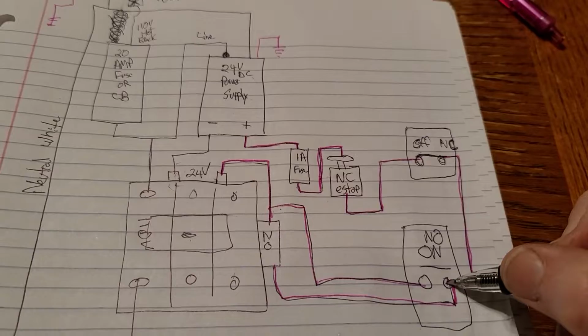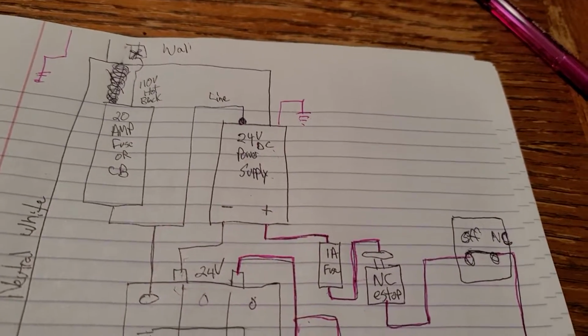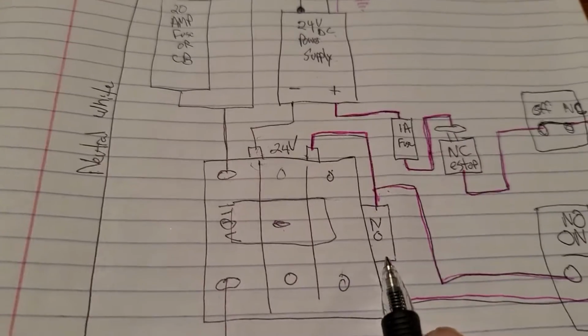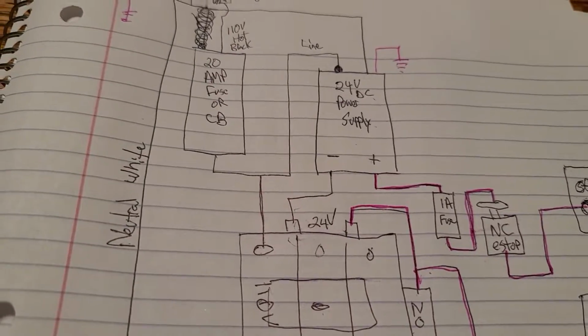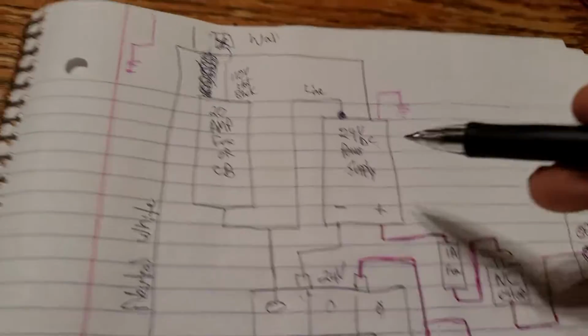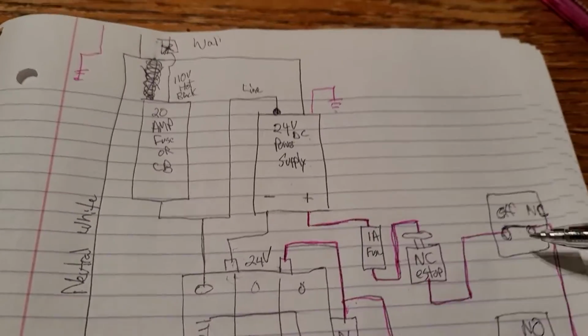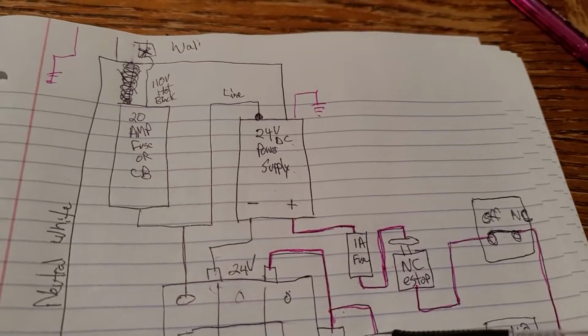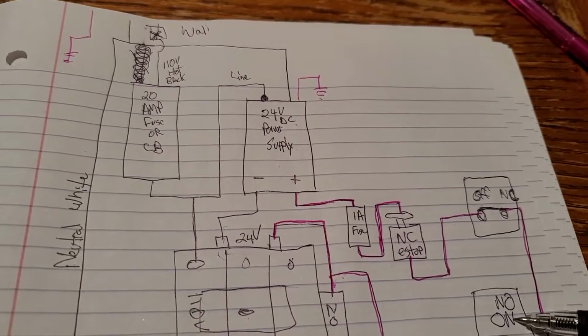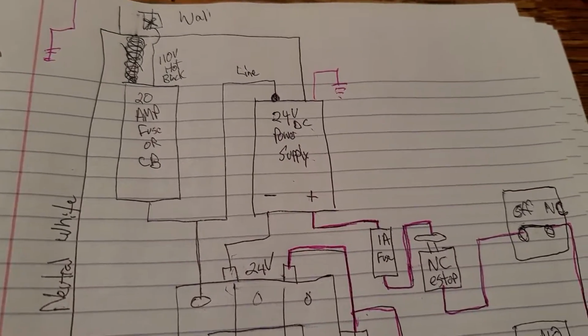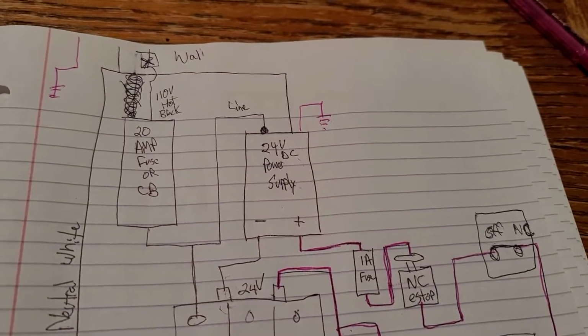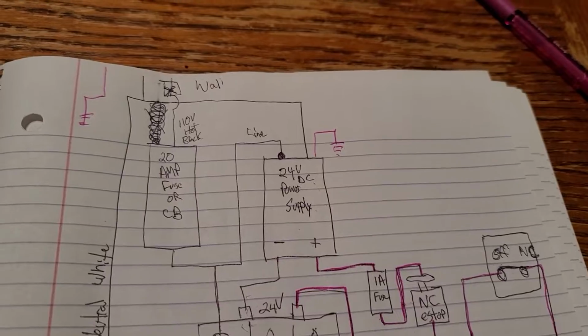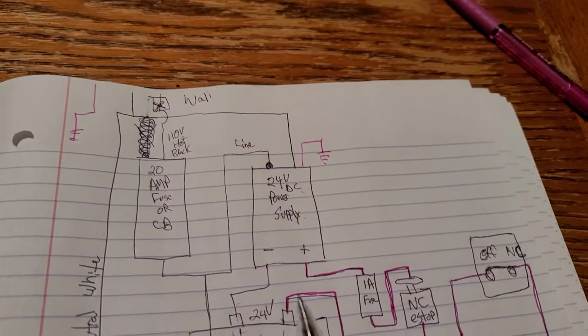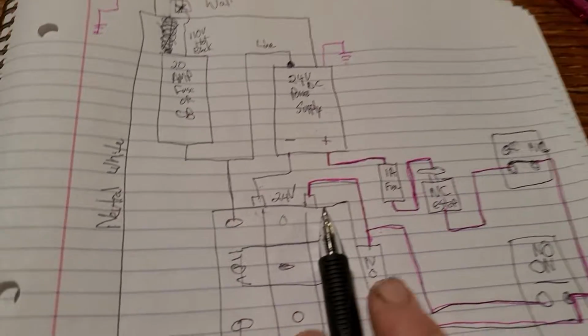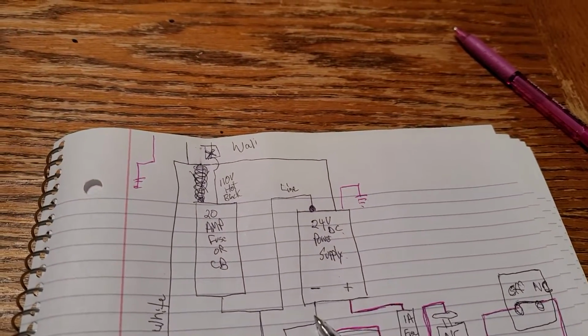And so when it comes, it goes here, but it also goes from where it connects. It also goes to an open spot over here on the contactor that's normally open, okay? So that means power, well, as long as it's plugged in and the disconnect's on, is always going all the way through here, but it stops because it's normally open here and it's normally open here. Okay? Now, the other half of the control is wired to the other side of the open. It's wired here, and it's wired to the other side of the normally open. Okay? And then it's wired to this connection on the coil right here. So, then we see that the common comes out and goes through here.